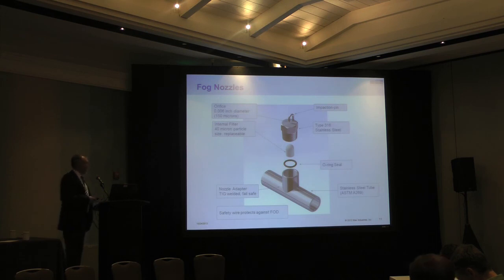This shows a typical fog nozzle. This is an impaction pin nozzle, which is our specialty. It has a 150 micron orifice and this impaction pin. So the water flows through the stainless steel tube, up through a nozzle adapter. There's an O-ring seal, a last chance filter. It comes out of the orifice in the center of that nozzle and breaks apart into fine spray. There's safety wires to protect against FOD. These are all TIG welded components. So it's quite safe to put it in the inlet duct.